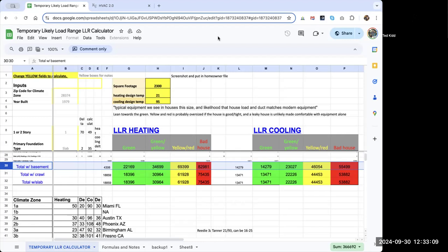And if you want good cooling, you need your ductwork to cool off, and then the room can get cooled. If you want good heating, you need the ductwork to heat up, and then the room will get heating. And so if it takes 10 minutes for the ductwork to heat up or cool down and your equipment only runs for 7, then those far rooms aren't getting heat or cool.